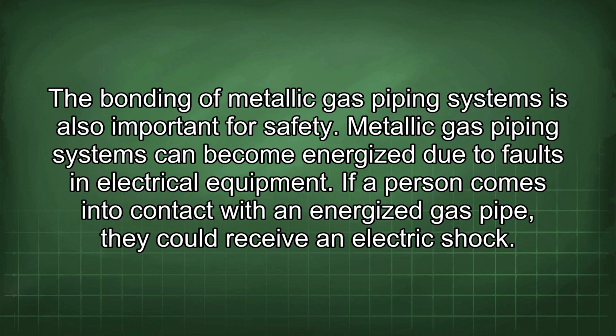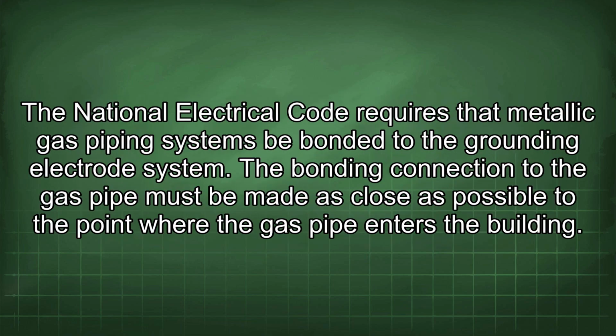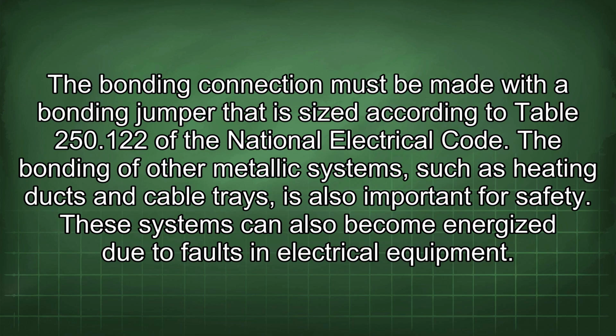The bonding of metallic gas piping systems is also important for safety. Metallic gas piping systems can become energized due to faults in electrical equipment. If a person comes into contact with an energized gas pipe, they could receive an electric shock. The National Electrical Code requires that metallic gas piping systems be bonded to the grounding electrode system. The bonding connection to the gas pipe must be made as close as possible to the point where the gas pipe enters the building. The bonding connection must be made with a bonding jumper that is sized according to Table 250.122 of the National Electrical Code.